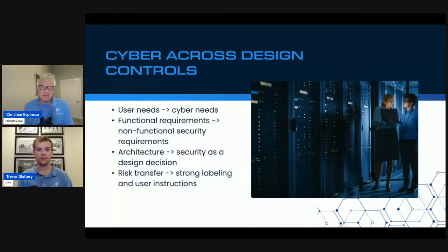So one of the considerations with cybersecurity and the design controls you have to look at is what the user needs are and what the cybersecurity needs are. There's a couple of distinctions here. Typically, when we're talking about user requirements to make the device work as intended, those are grouped into functional requirements, like what is required to make the device function and do what we want it to do. But then we have the non-functional requirements, which are the cybersecurity requirements. They're not required for the device to function, but they're required for the device to be secure. And those need to be designed into the product.